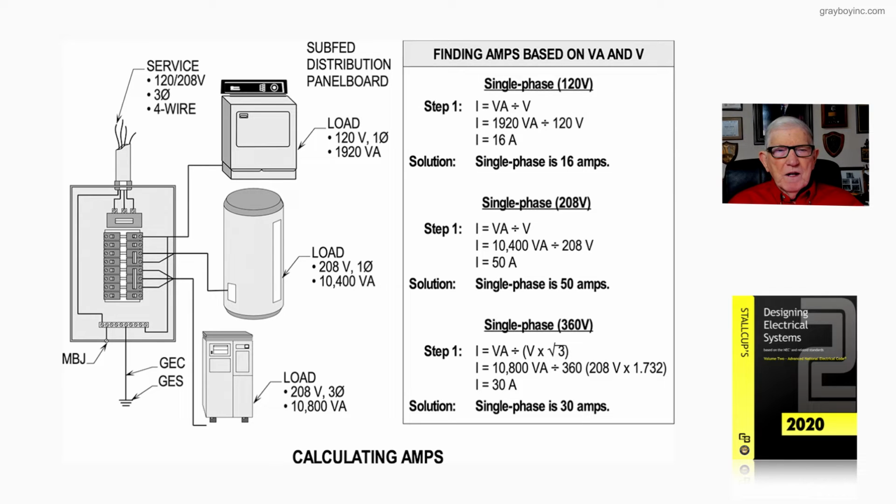So the load from that circuit breaker over to that unit would be 16 amps. But you would calculate it at 125% if it was continuous. If the load operated less than 3 hours, then it wouldn't be considered continuous by the definition of continuous operation or continuous duty in Article 100, so we'd remain at 16 amps.